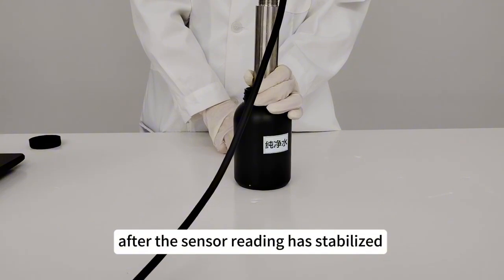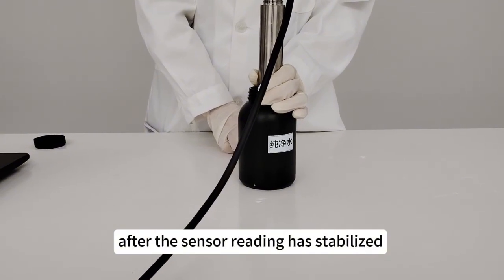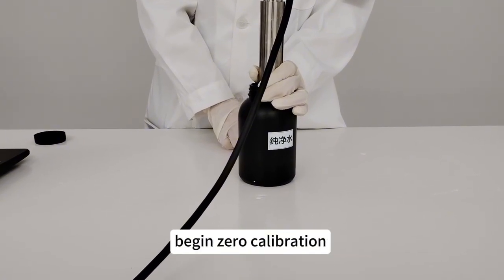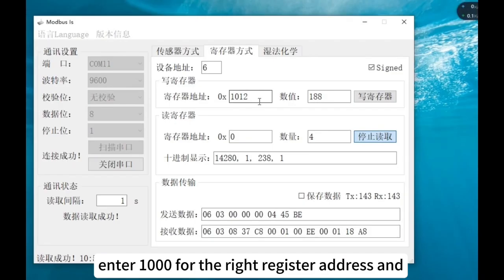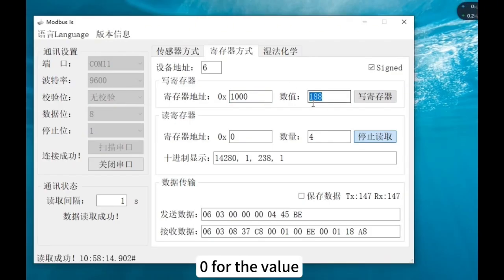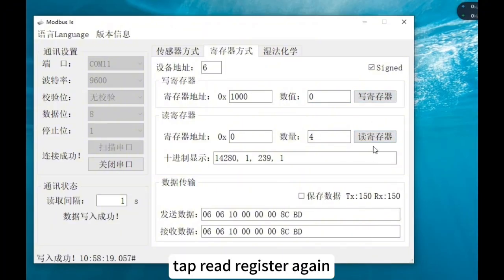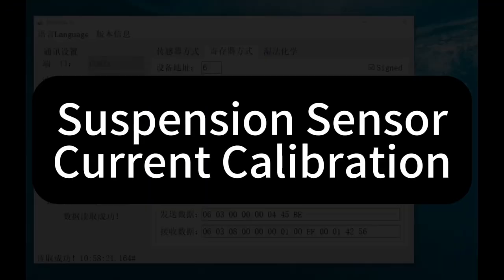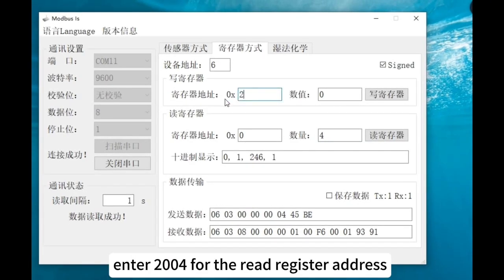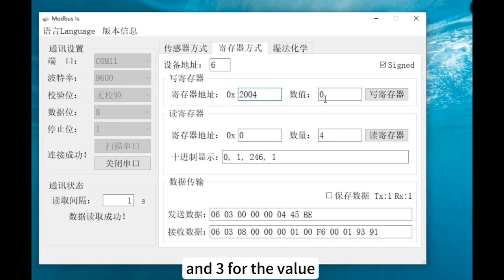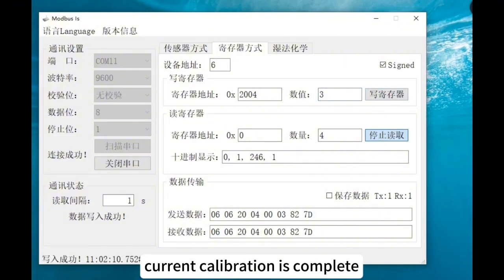After the sensor reading has stabilized, begin zero calibration. Enter 1000 for the write register address and 0 for the value. Write register. Tap read register again. Enter 2004 for the write register address and 3 for the value. Tap write register. Tap read register again. Current calibration is complete.